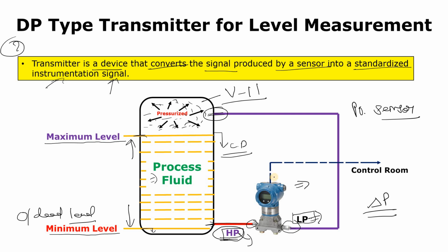From the transmitter, which we have already discussed, the signal will go to the control room. When the signal goes to the control room, in the DCS panel you will see the level of this vessel, let's suppose you will see the level at 50%. So the signal that goes there will be directly proportional to the level of the vessel or level of the tank.